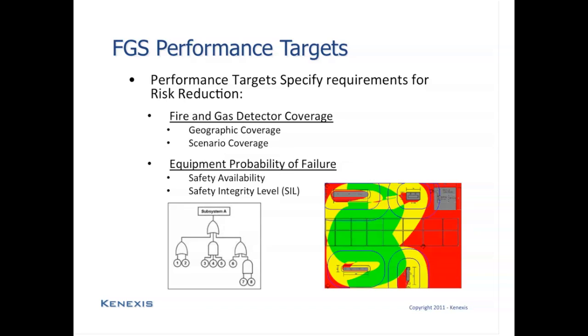In addition to calculating coverage or setting performance targets for coverage, we will also set targets for probability of failure on demand of the electrical equipment, the safety instrumented function, if you will. Now, the ISA 84.00.07 technical report specifically defines the metric that we're trying to achieve in terms of safety availability, because the writers of that standard believe that a safety availability metric is more appropriate than the SIL, specifically because very high SIL targets, such as SIL 3 and SIL 4, are nonsensical for fire and gas system design.